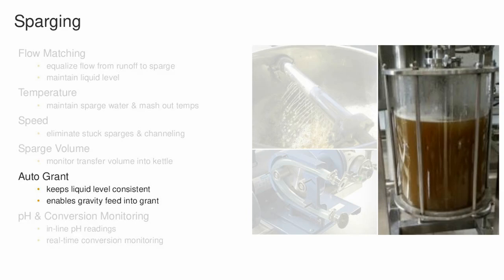But if you just have one float, what can happen is that you're going to turn that pump on and off pretty rapidly, which could also start causing some issues with the pump and the motor starts overheating. So if you have a second float, which is usually set a little bit higher, closer to the top, what happens is when it hits the bottom float, it'll go at a slow speed, and that liquid level will start rising as you're pumping over. Now, if it hits that top level switch, then it's just going to kick to a higher speed until it gets down to the lower switch, and then it starts that cycle all over. That's a very nice way to handle an auto grant setup.